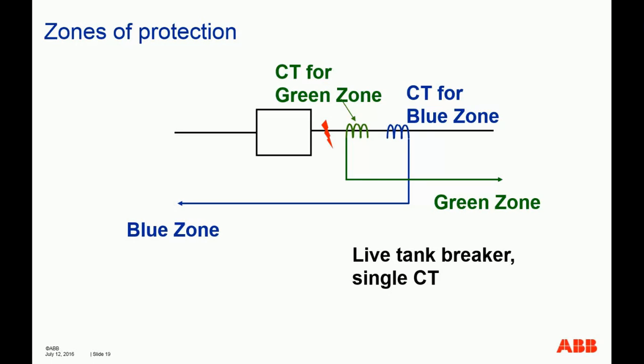However, if the breaker is currently closed and carrying load, the blue zone trips. However, the green zone will restrain and will not trip. So the fault is actually not cleared, because it's still being fed by the contribution on the right-hand side from the green zone sources.